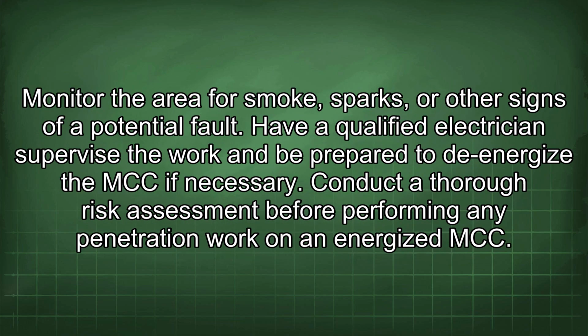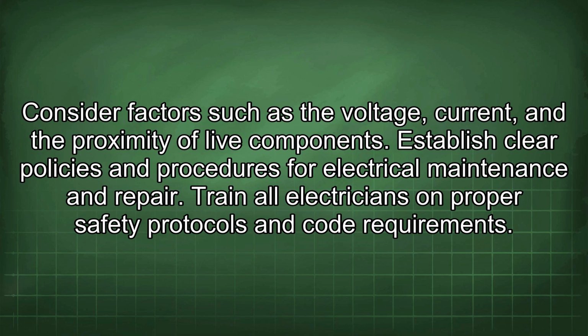Monitor the area for smoke, sparks, or other signs of a potential fault. Have a qualified electrician supervise the work and be prepared to de-energize the MCC if necessary. Conduct a thorough risk assessment before performing any penetration work on an energized MCC. Consider factors such as the voltage, current, and the proximity of live components.